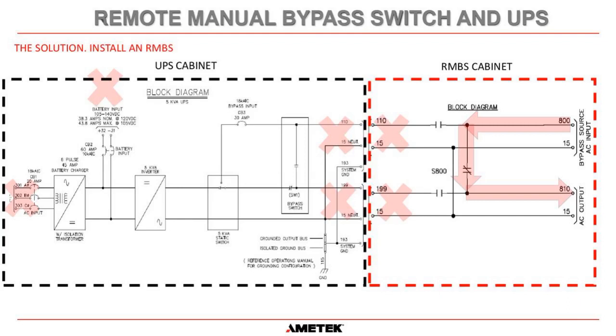But what you can see here is, if we isolate the AC input at the MCC, if we isolate the battery input at the batteries themselves or at a disconnect outside of the UPS cabinet, and we use our RMBS cabinet to go into bypass, you can see here that bypass would flow here. And you can see this contact here is open. This contact here is open. That makes these terminals volt-free. These terminals volt-free, which then makes the terminals inside the UPS volt-free.